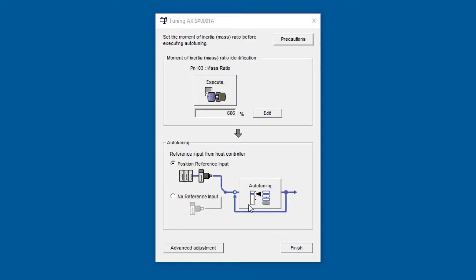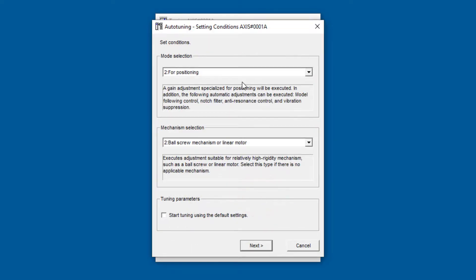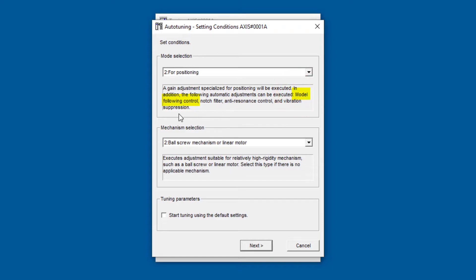And now I'm ready for auto-tuning with position reference input, which will be from program jog. Auto-tuning, and you see that this default mode here, mode 2 for positioning, does list model following control and vibration suppression.